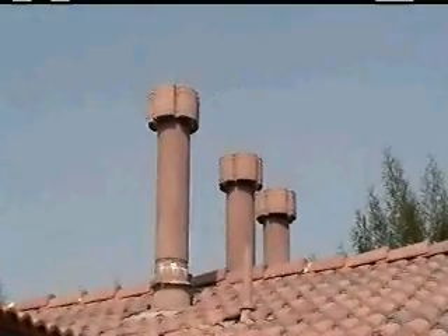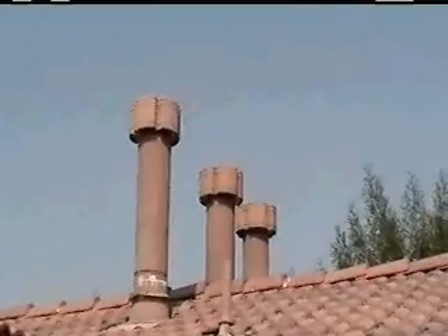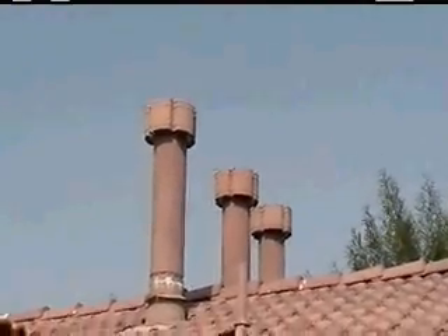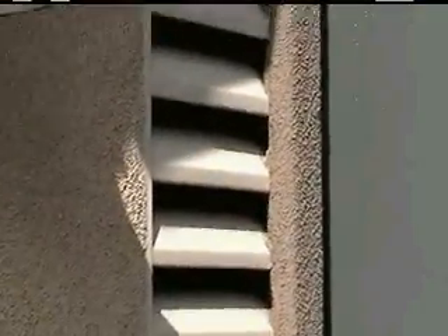As we approach this particular heater repair job, you'll notice the correct vent stacks on the outside of the building. You'll also notice an upper and lower airflow, which is very important to make sure we have enough fresh air makeup into the room for the heaters to operate properly.